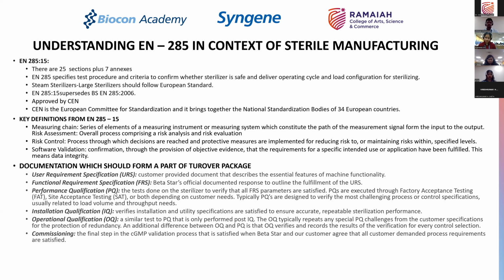Okay. Now, I have picked up one section on the autoclave, which says what is the minimum documentation which should form a part of a turnover package. So the first one is what is called a URS. What is a URS? It's a user requirement specification.